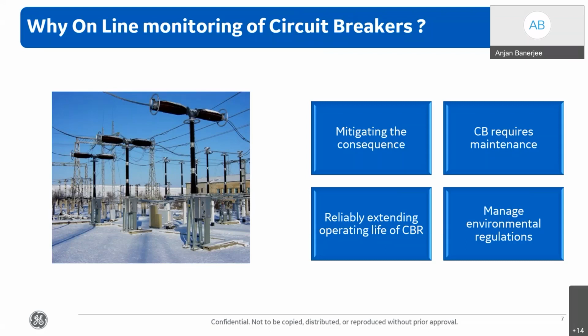Another important part is that the circuit breaker is one of the most dynamic pieces of equipment, where the contacts are traveling in milliseconds. We have arcing current during fault interruption, and SF6 is pumped in to extinguish the arc. That means the circuit breaker components need regular maintenance, not time-based, but condition-based. If we have condition-based maintenance with online monitoring equipment, we would be able to identify which component is faulty, and by replacing that component, we would be able to extend the operating life of the circuit breaker reliably.